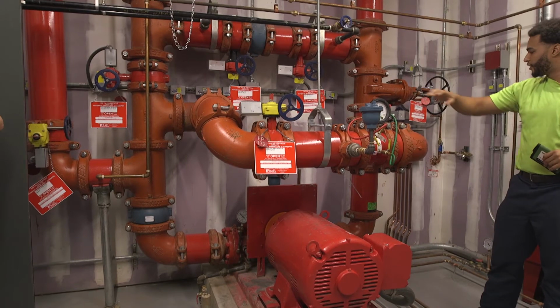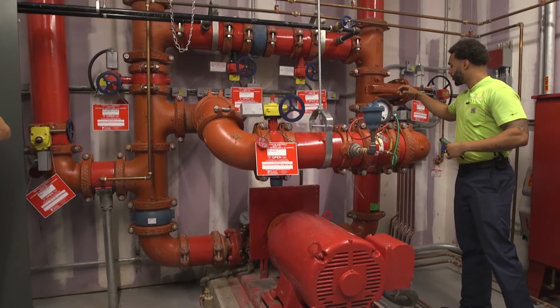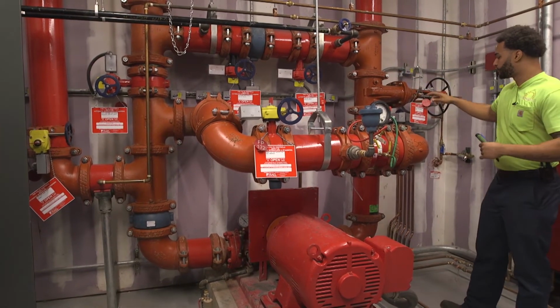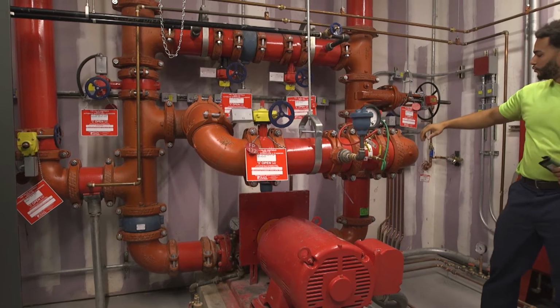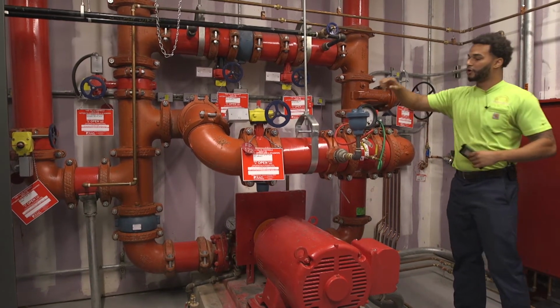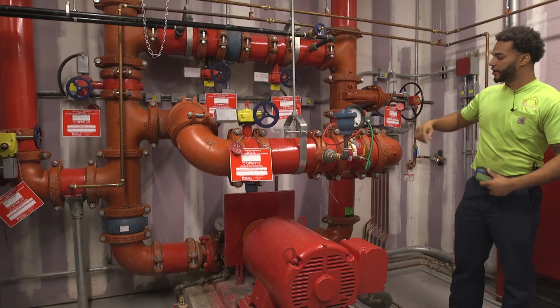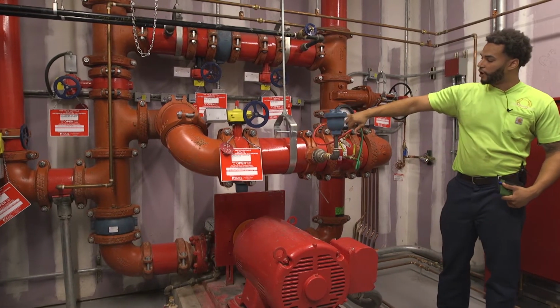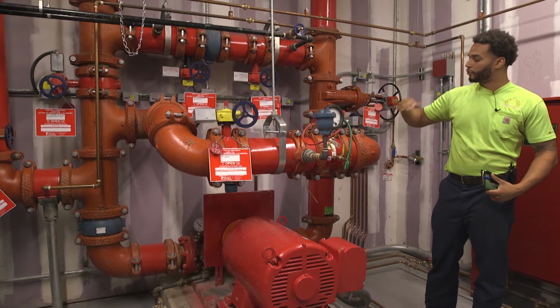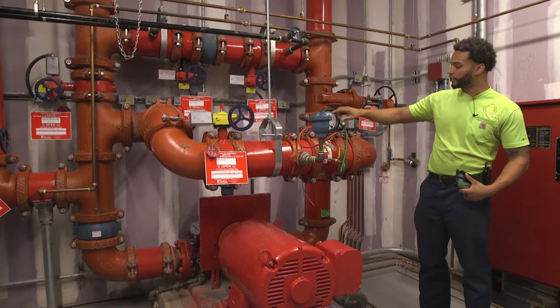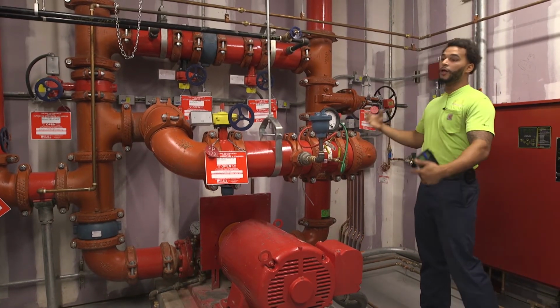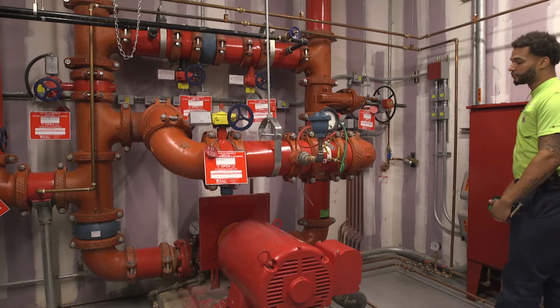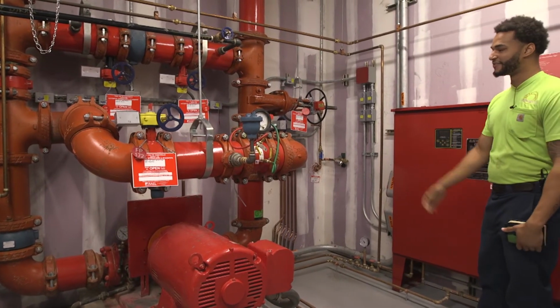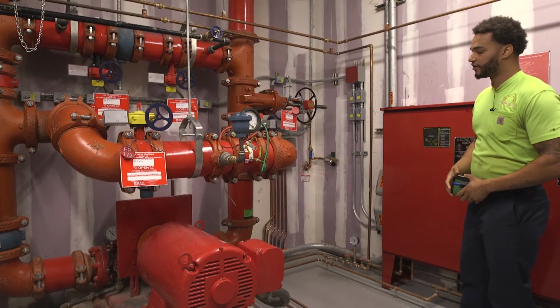So this flow meter here, as you guys can see, I apologize, I missed it, is made up of 2 isolation valves, butterfly valves. And basically we're gonna open our suction side and we're gonna be throttling on our discharge side there. This gauge here is gonna start climbing. Once we hit our desired GPMs, we're gonna hold it there, we'll bleed it, and that's an acceptable way to test there. That's just another testing form there.